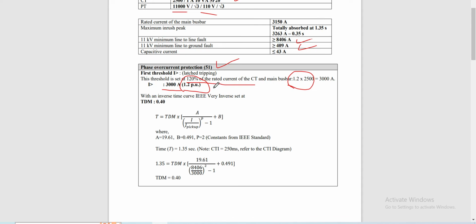This is how we got this 1.2 per unit. We adopted the IEEE very inverse curve as our inverse time curve, and our time dial multiplier is set at 0.40. How did we get this value? By using this equation, with the following constants from the IEEE standard for A, B, and P, and our first threshold is set at a time of 1.35 seconds.